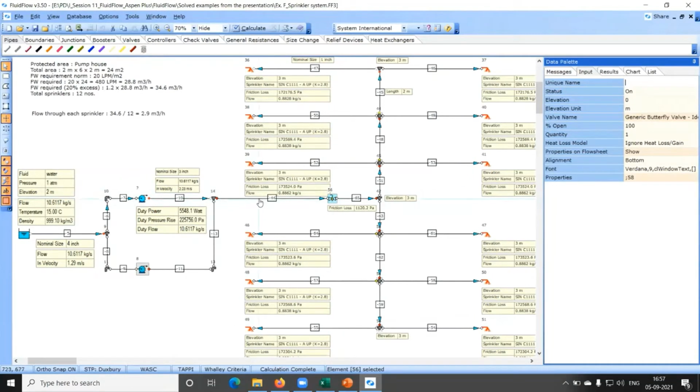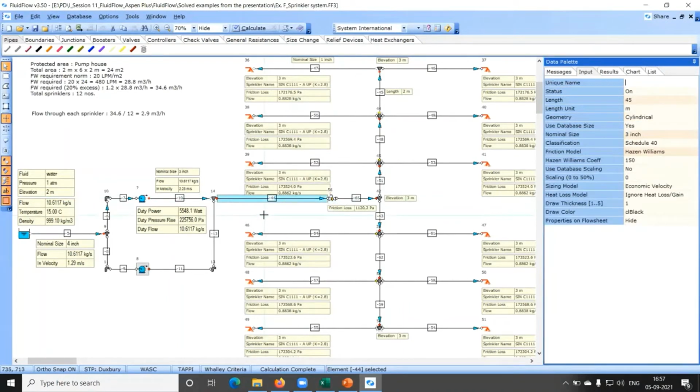All the water which is there will try to go to the pump house, right? So what happens to the pressure? It was before 5 bar gauge. The pressure will reduce. So from 5 bar gauge, it will go to say 5.8, then 5.5. So maybe 5.5 is the set point for the main pump to start, right?